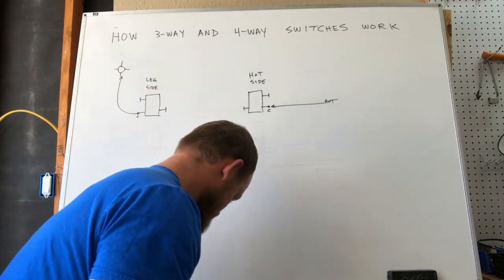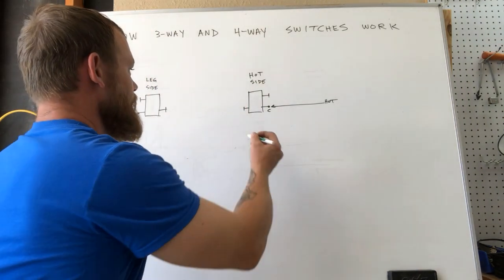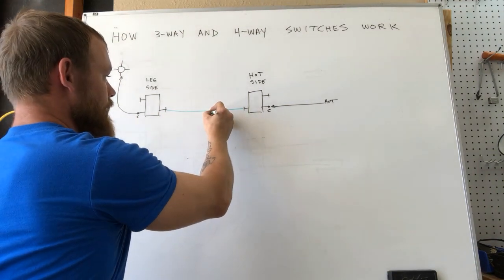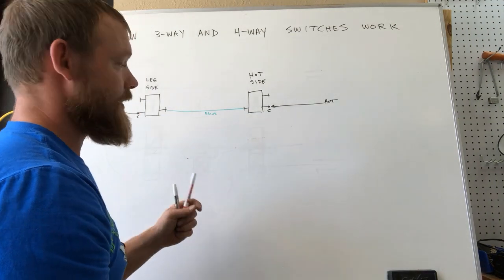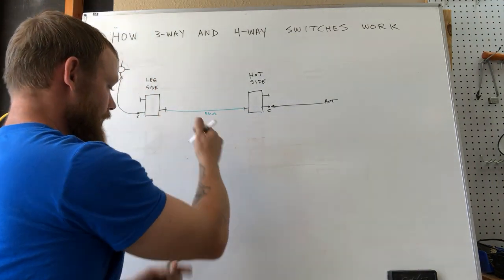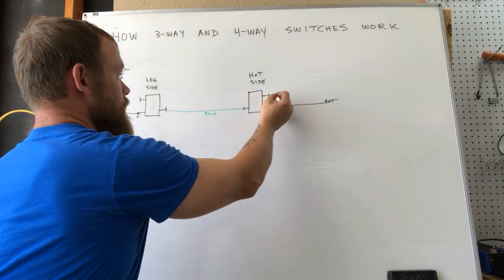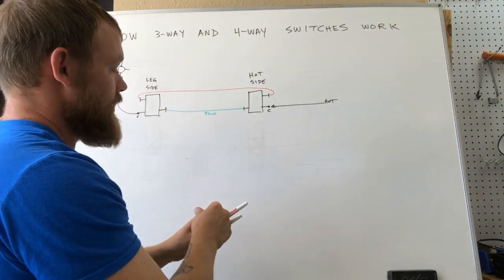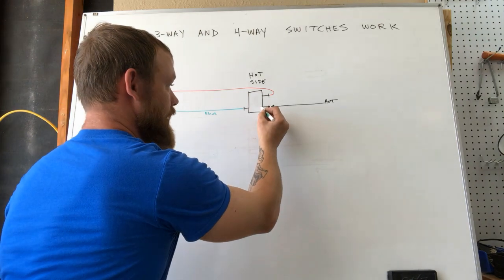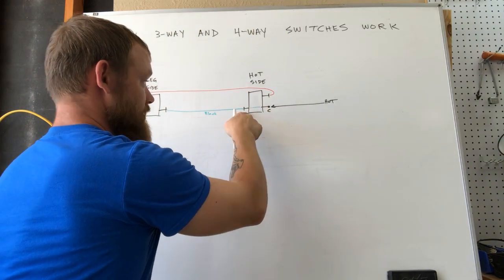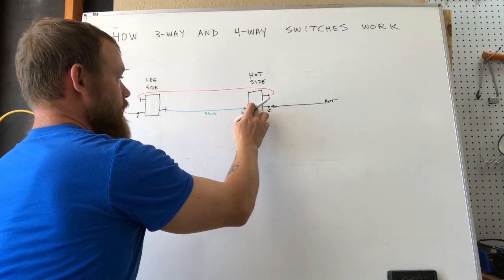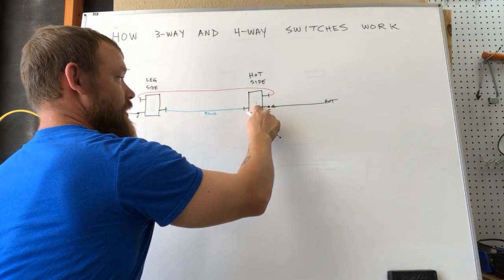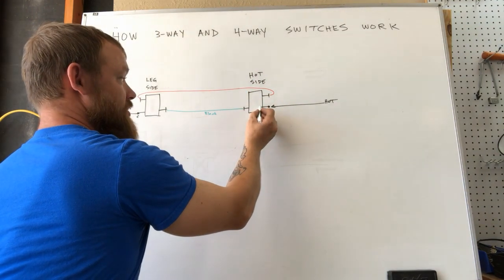So we've got one traveler that you would run from this device to this device, and we'll call this your black. I realize it's not black, it's blue, but in a 12-3 and travelers that you're going to run, you're going to run one black conductor and you're going to run one red conductor. So the inside of a three-way switch is going to either connect this common terminal to this terminal, or it's going to connect to this terminal. So if you push the switch in one position, it connects these two. If you push the switch in another position, it connects these two.